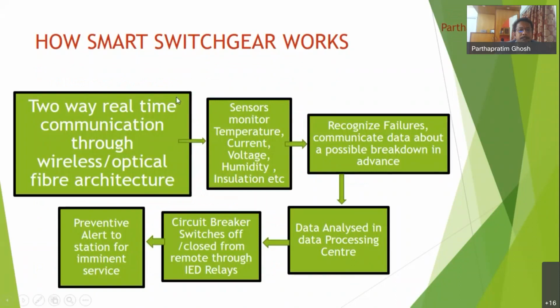How does smart switchgear work? From the left, there is two-way real-time communication through a wireless and optical fiber architecture. There are sensors which monitor temperature, current, voltage, humidity, insulation, and many other factors. They recognize failures and communicate data about a possible breakdown in advance. Then data is sent to the central data management system, where it is analyzed. A remote signal goes through IED relays to make or break a circuit breaker remotely and automatically, based on the nature of the faults.